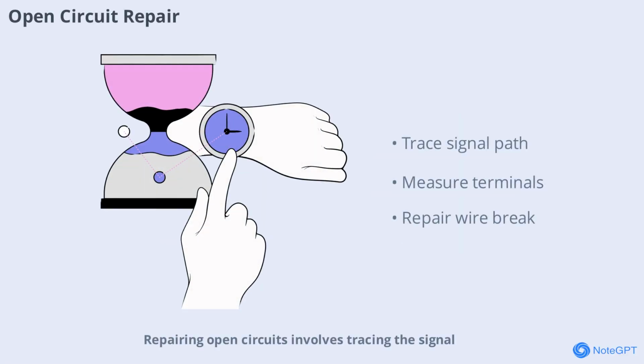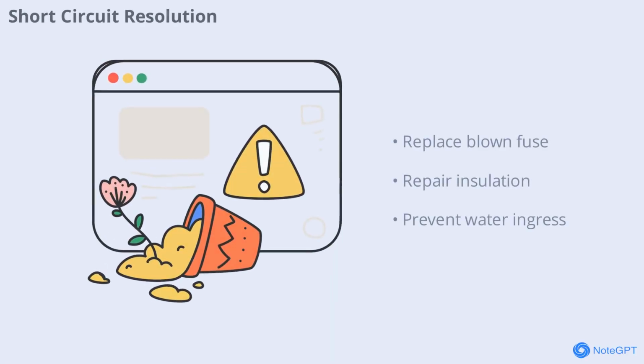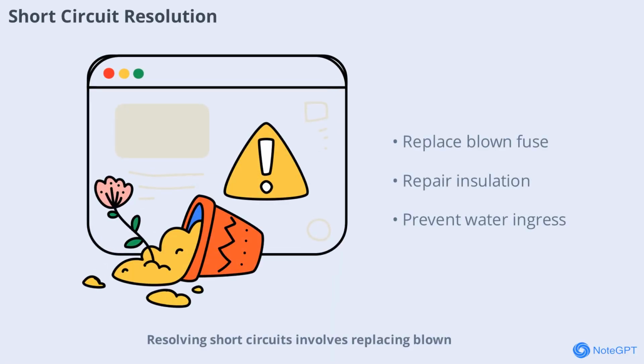Repairing open circuits involves tracing the signal path and measuring voltage or current across terminals. Once the wire break is located, repairs restore proper signal flow and system accuracy. Resolving short circuits involves replacing blown fuses and repairing damaged cable insulation. Preventing water ingress and ensuring proper cable routing are essential for system safety and reliability.